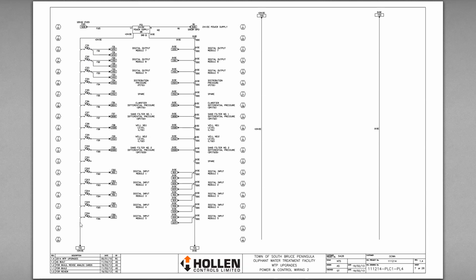What's important when you look at these is if you saw a 50 amp fuse here for a PLC input card, that's a problem, because if you were to have a short and 50 amps actually came into it, there's no way it would survive that. Not only might you destroy your PLC card, but you could destroy your 24-volt power supply because its circuitry can't output that. It's probably limited somewhere, so you might not blow it up, but you might lose all your 24 volts on this side. If you lose your 24 volts on this panel, you lose all your cards, because all of your cards are DC modules.